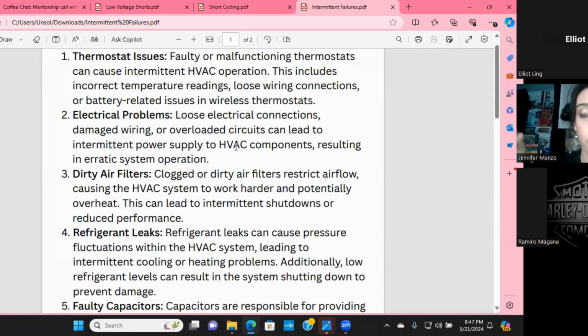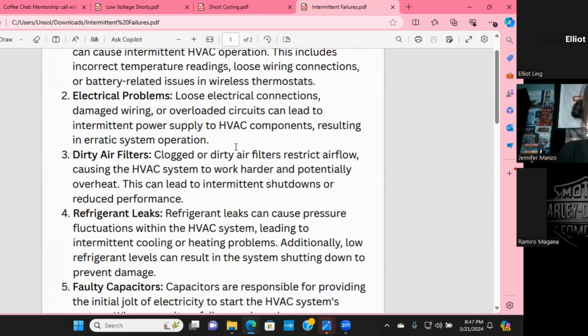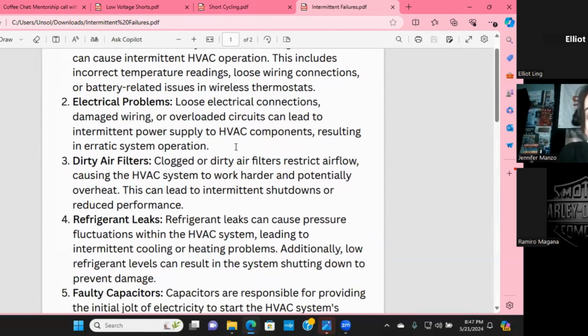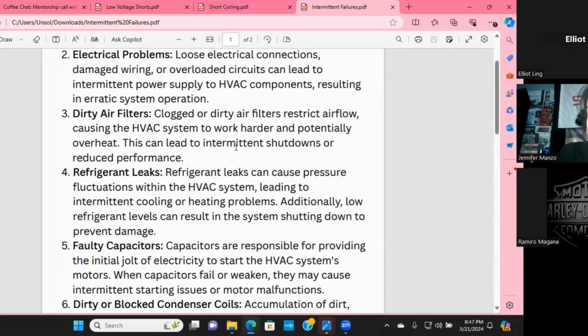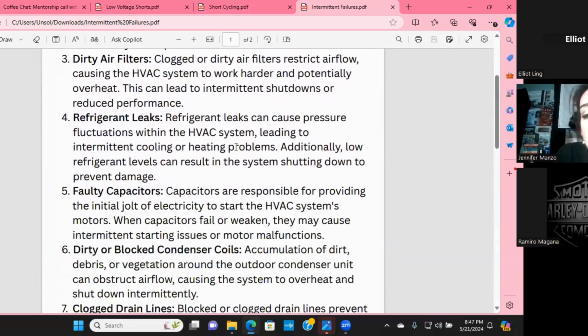Gas valves are known for it. You guys who work on boilers and furnaces know exactly what I mean. RTUs as well. Gas valves are known for it. And usually if you give them a little smack with your adjustable hammer, quote unquote, you'll get it to come out of it, but not always. And sometimes it can really cause something that you're chasing down for long periods of time. So we want to go over this just a little bit to make sure that that's not dragging you guys onto a roof at 9 PM ever. Dirty filters. We've talked about dirty filters. You guys, it is such an easy thing that you can do.